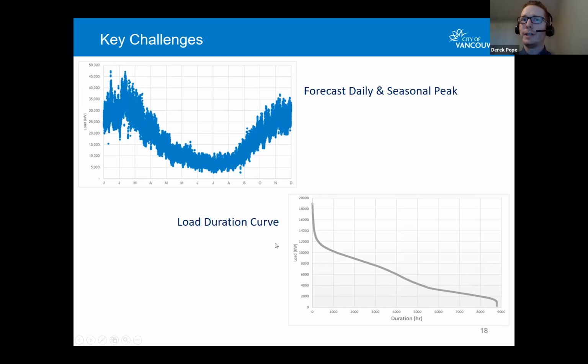This load duration curve gives you a sense of, from last year, what our demands were in kilowatts and the number of hours at that demand. For less than 1,000 hours per year, we can see demand as high as 20 megawatts, whereas for the other 7,000 hours per year, it would be under 10 megawatts.